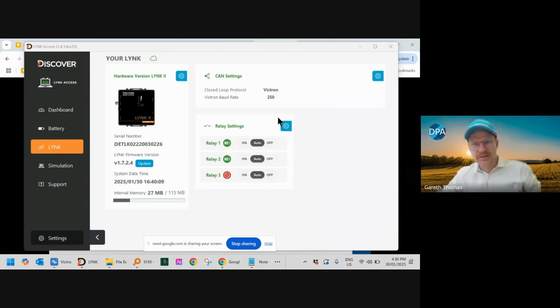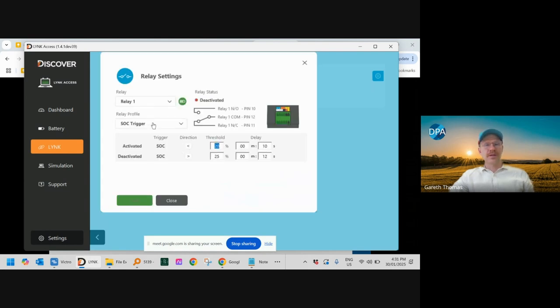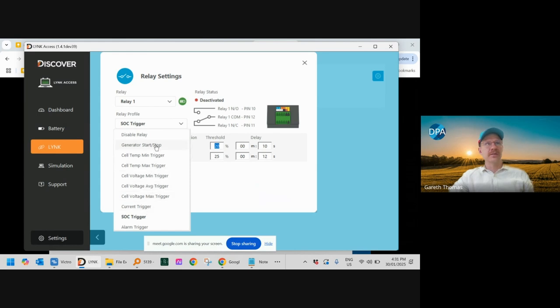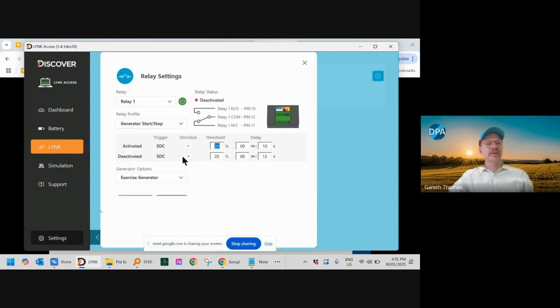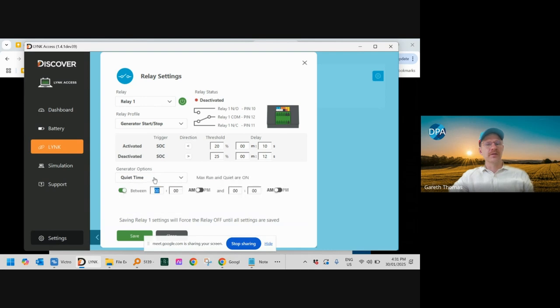So when we're in here, we press this cog relay settings, and then up comes this menu. You've got the 3 different relays, and then there are various parameters that you can set that relay to be triggered by. It's a normally open, normally closed relay. The most common one you'd be using would be this generator start-stop relay, which can be determined by state of charge. Then you've got generator exercise, quiet time, and max run time. You can use all 3 of these, it's not either or, all of these options are available. So it's a pretty comprehensive generator start-stop setup, nearly as good as the Victron one, I think.